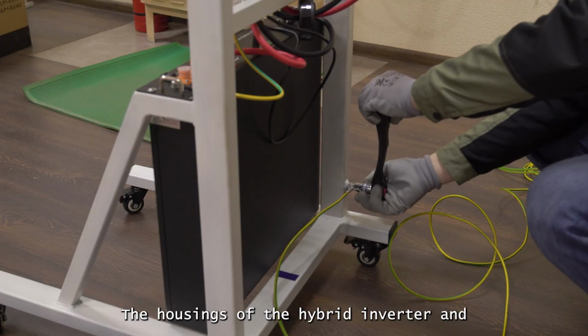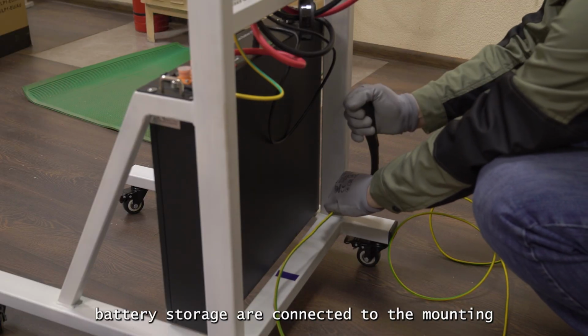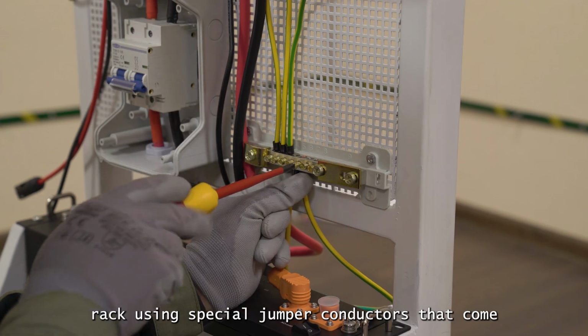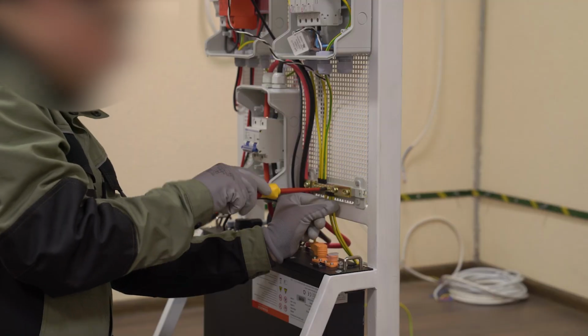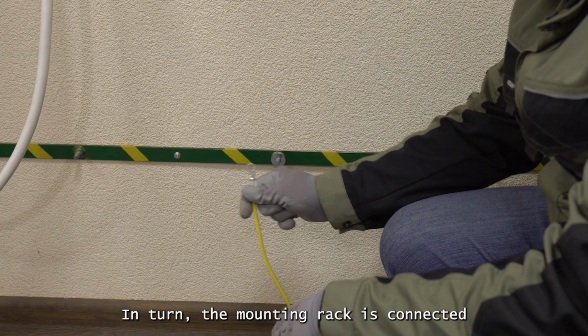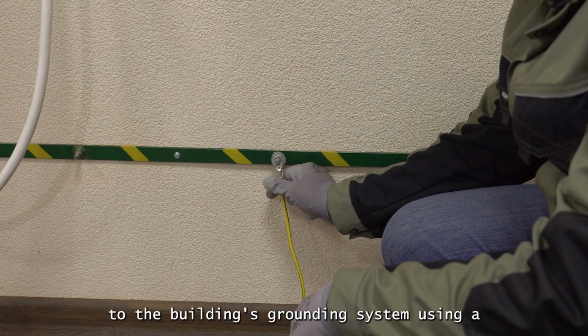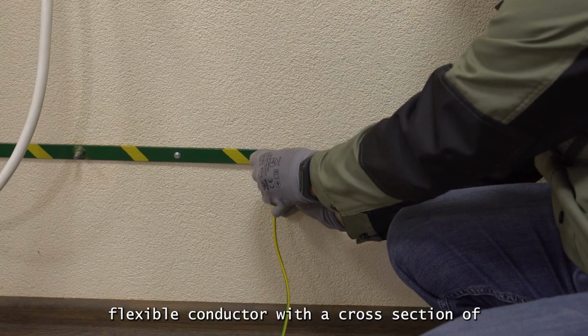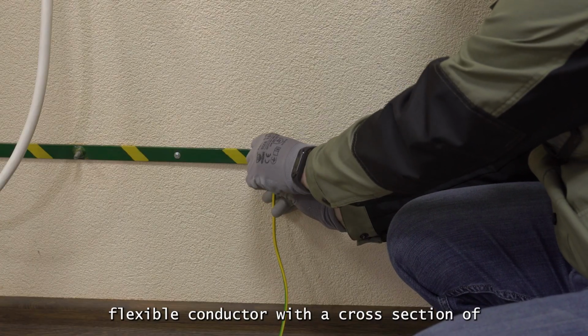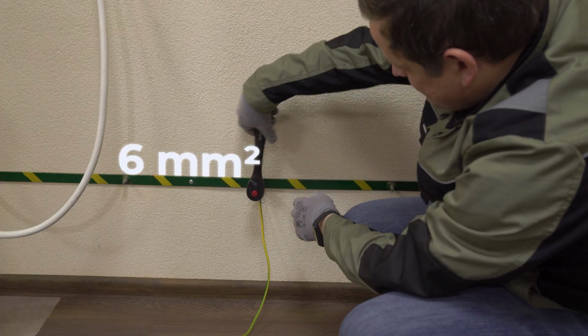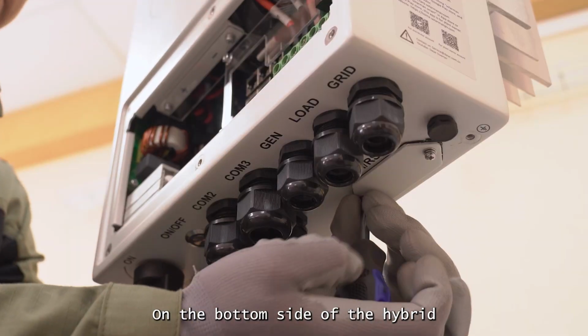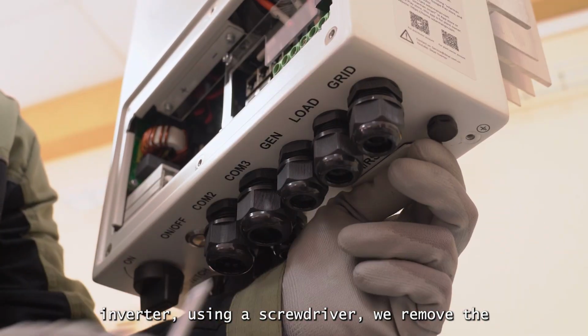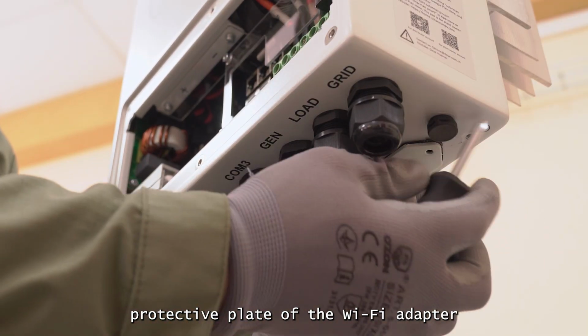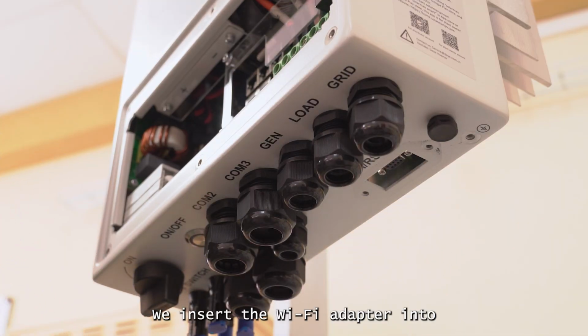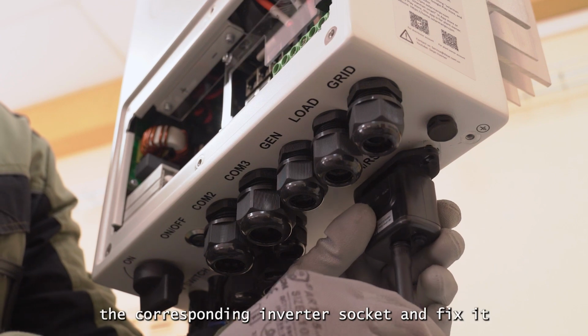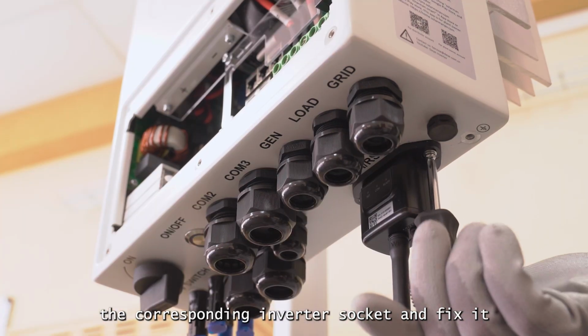The housings of the hybrid inverter and battery storage are connected to the mounting rack using special jumper conductors that come with the kit. In turn, the mounting rack is connected to the building's grounding system using a flexible conductor with a cross-section of at least 6 square millimeters. On the bottom side of the hybrid inverter, using a screwdriver, we remove the protective plate of the Wi-Fi adapter port. We insert the Wi-Fi adapter into the corresponding inverter socket and fix it using screws.